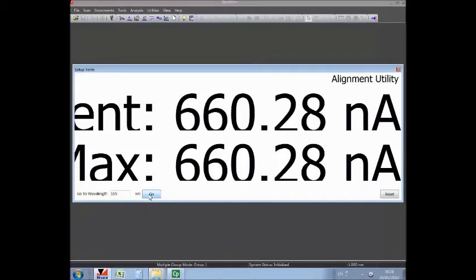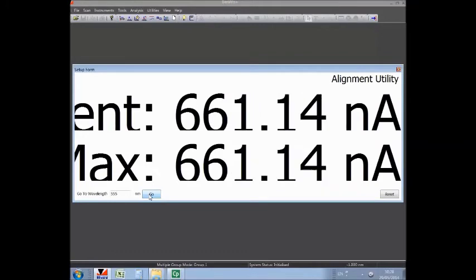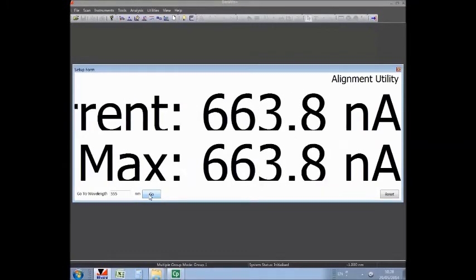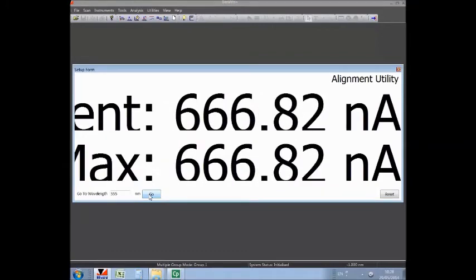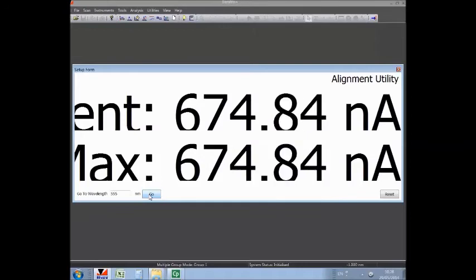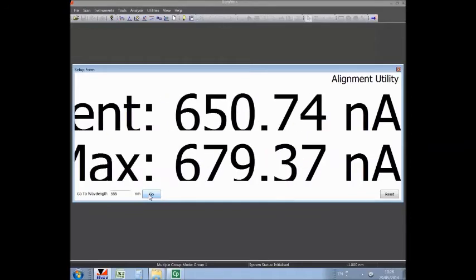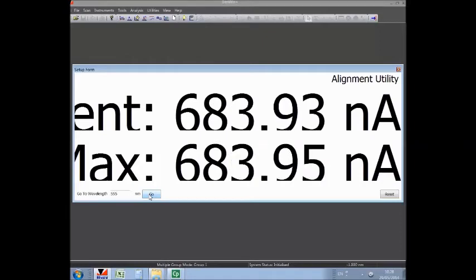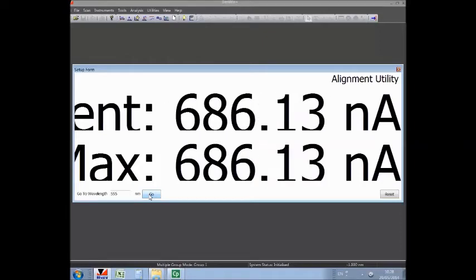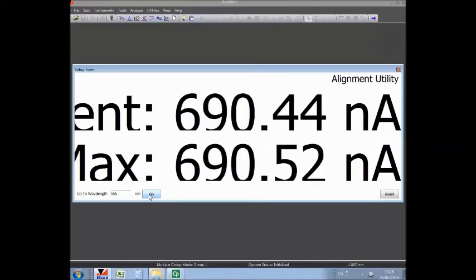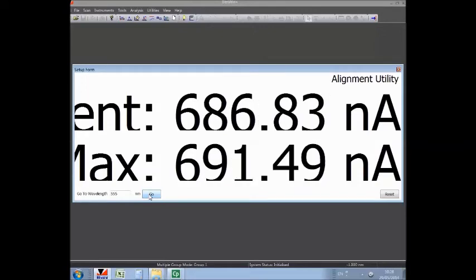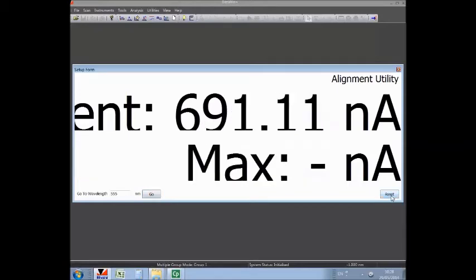And we should pay attention again to the direction of the peak intensity emitted from the source, and we should pay attention to obtaining as high a value as possible, since as opposed again to the spectral check relative measurement, we are now performing an absolute measurement which will form the measurement result for this source. The maximum can be reset where one desires.